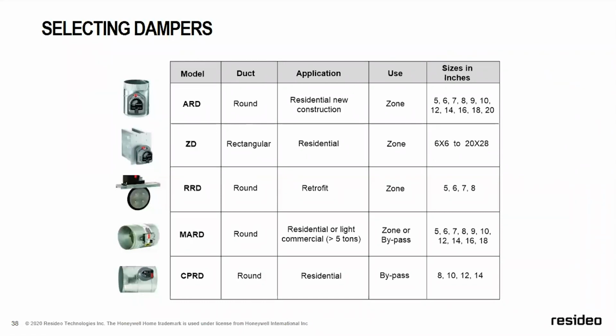The RRD, or retro round, for retrofit, 5, 6, and 8. The MARD is typically for light commercial, anything over 5 tons. And then we have our CPRD, which is constant pressure relief damper. This is for our bypass. 8, 10, 12, and 14. We'll get into that a little bit later.